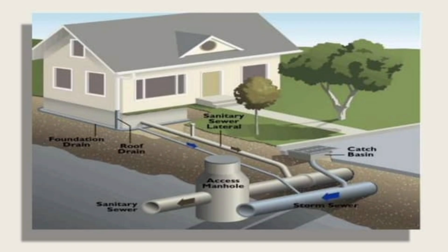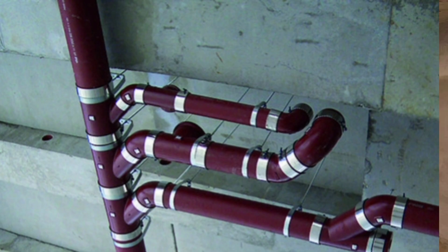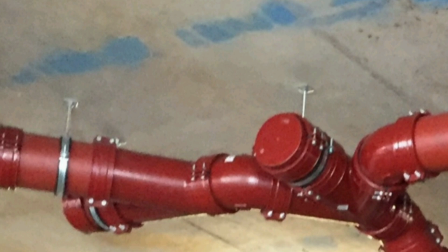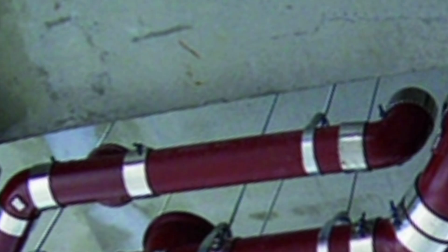7. Drainage pipe installation. Before installation, the plumber should check the approved drawings and pipe routing. First, mark the pipe route and required levels. Then install the pipes with the specified slope. Make sure joints are properly connected and supported. Provide cleanouts at the required locations for future maintenance. After installation, check the alignment, slope, supports, and connections. Finally, carry out the required testing before closing the ceiling, shaft, or wall.